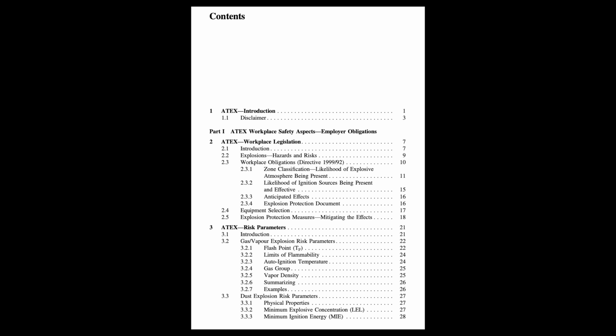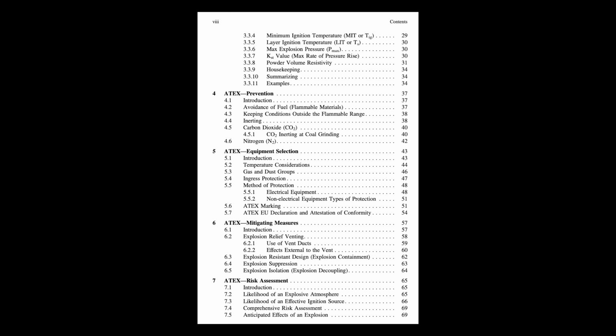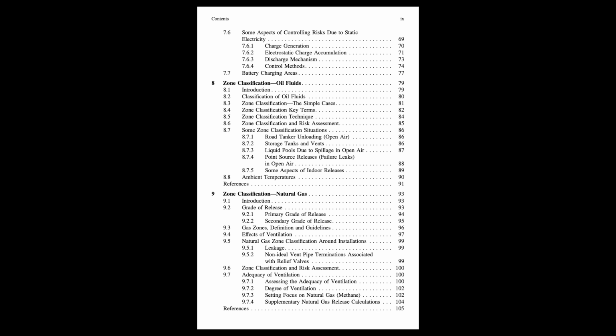Okay, so prevention is plan A. Avoid the material, control the concentration, or inert the atmosphere. But the guide also admits that sometimes you just can't completely prevent an explosive atmosphere from forming. What happens then? Right. Sometimes the process inherently creates the risk. In those cases, we have to move to mitigating measures. If we can't eliminate the possibility of an explosion entirely, we need strategies to minimize the damage if one does occur. Backup plans.